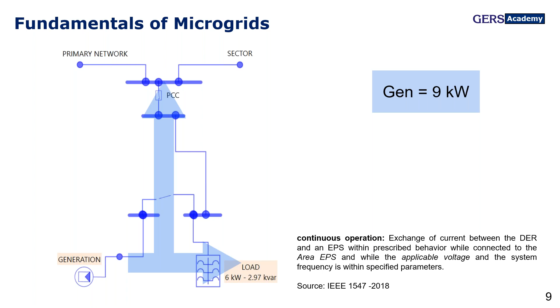And the first case that we will see, on this very simple situation where we have this load of 6 kilowatts, the PV generation facility and the connection to the distribution utility, is that we generate, say, in the PV facility 9 kilowatts, which of course is larger than the load. So if we have this situation, we can imagine that there will be a surplus, of course, 3 kilowatt surplus. Our load takes 6 kilowatts. The PV generates 9 kilowatts. And this is the typical case, according to the IEEE 1547-2018, that we have a continuous operation, where basically our PV facility feeds the associated load and the surplus is sent to the distribution system.